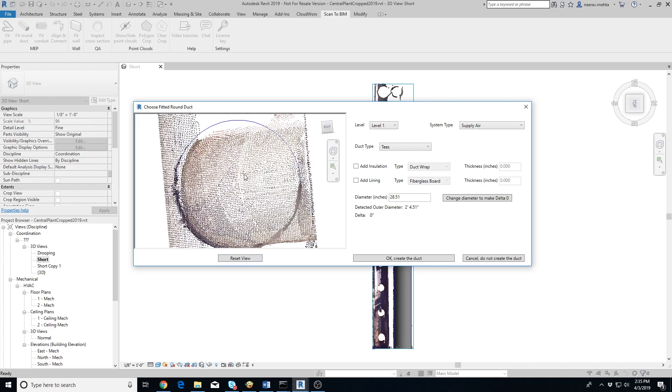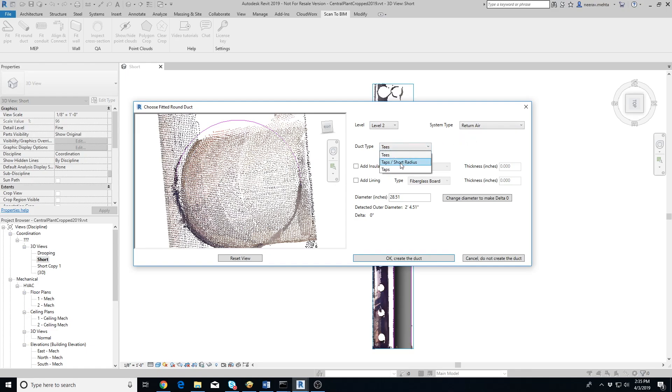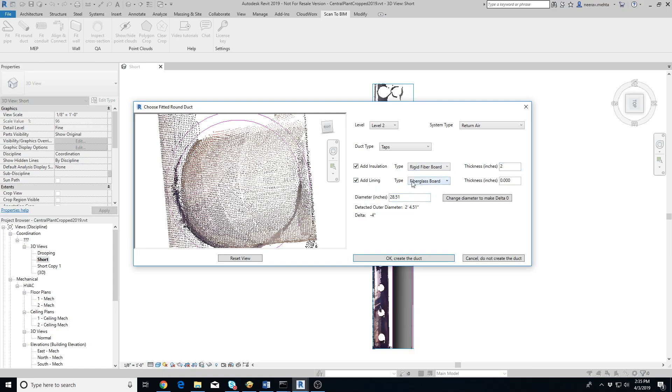On the right side, you can select the duct's level, system type, and duct type. If the duct has insulation, click on Add Insulation checkbox, select the type of insulation and the insulation thickness. If the duct has lining, then click on Add Lining checkbox, select the type of lining and the lining thickness.